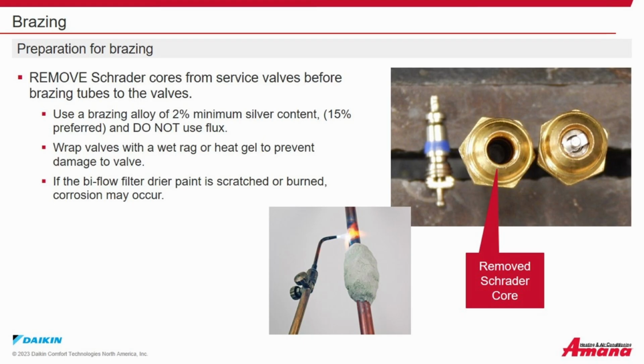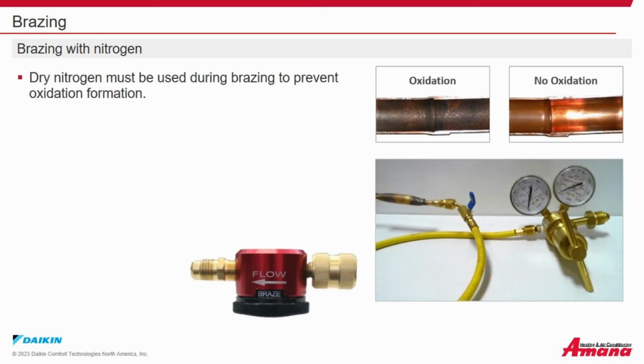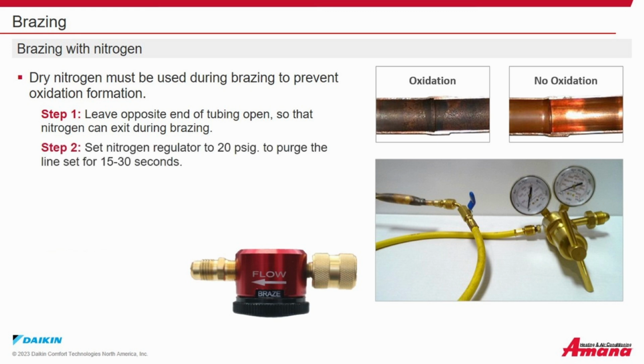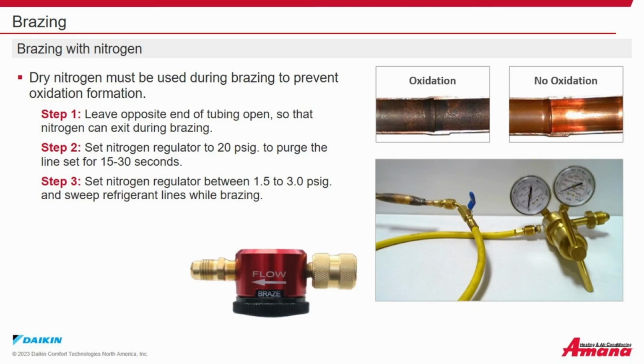Brazing with nitrogen. Dry nitrogen must be used during brazing to prevent oxidation formation. Step 1. Leave the opposite end of the tubing open so that the nitrogen can exit during brazing. Step 2. Set the nitrogen regulator to 20 psi to purge the line for 15 to 30 seconds. Step 3. Set your nitrogen regulator between 1.5 and 3 psig to sweep refrigerant lines while brazing.